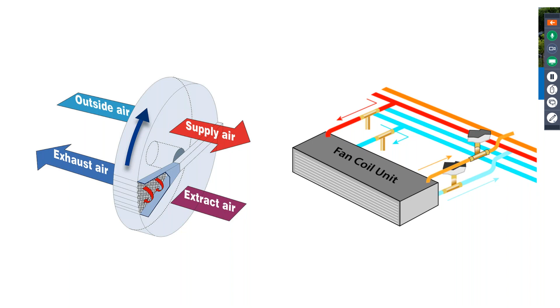In addition, because most of the fume hoods are now filtered fume hoods, all of the exhaust from the building, except for the 4 ducted hoods that remain, all of that general exhaust air from the room is just clean room air. And so you can use enthalpy wheels for heat recovery, which are far more effective than a traditional glycol runaround system. And so that, again, further reduces the loads on the building.